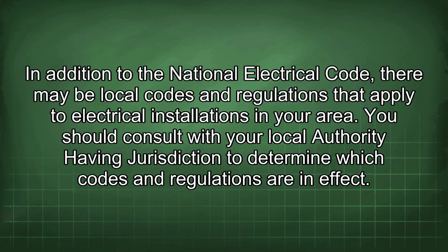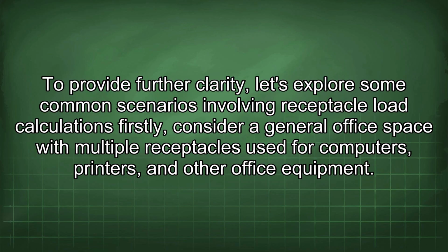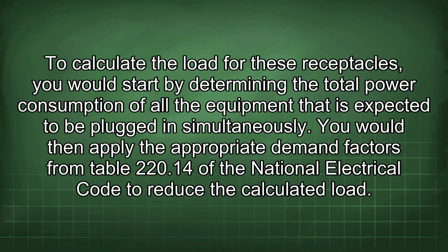In addition to the National Electrical Code, there may be local codes and regulations that apply to electrical installations in your area. You should consult with your local authority having jurisdiction to determine which codes and regulations are in effect. To provide further clarity, let's explore some common scenarios involving receptacle load calculations. Firstly, consider a general office space with multiple receptacles used for computers, printers, and other office equipment. To calculate the load for these receptacles, you would start by determining the total power consumption of all the equipment that is expected to be plugged in simultaneously.